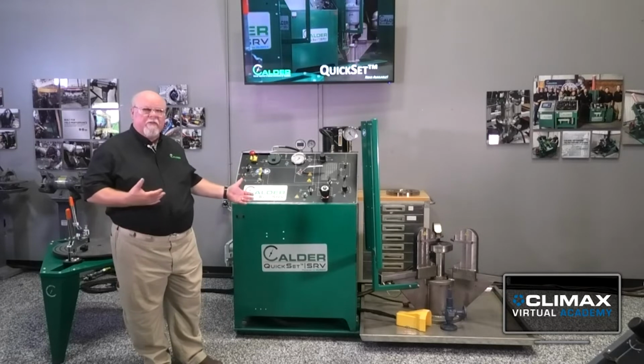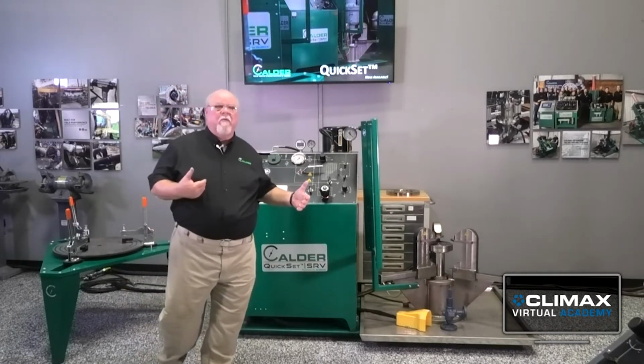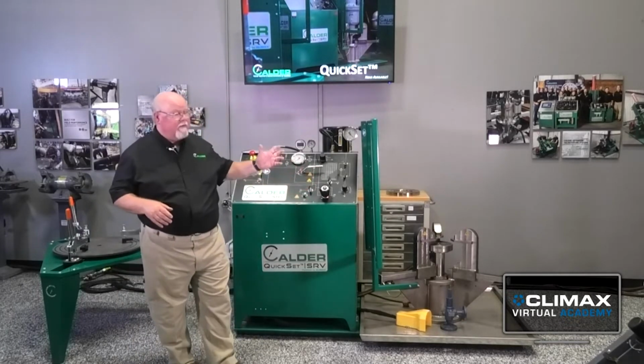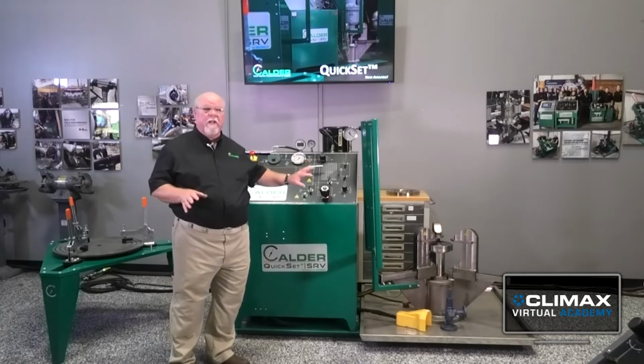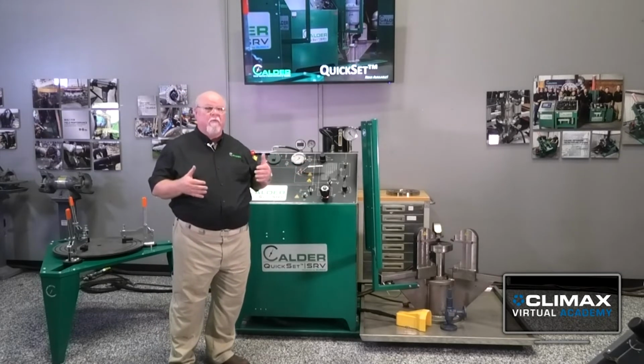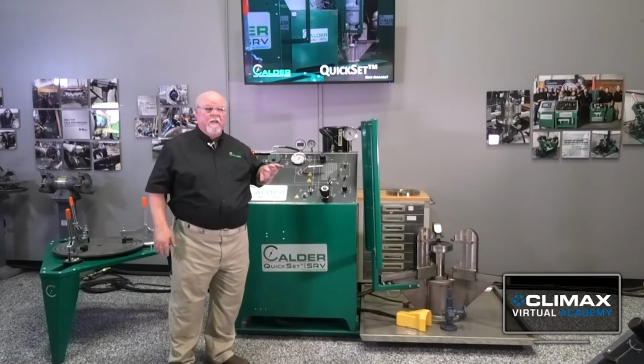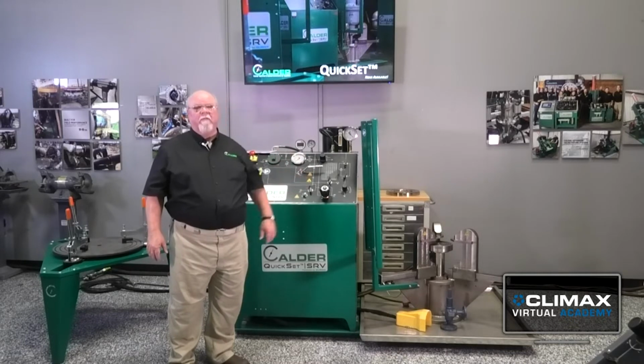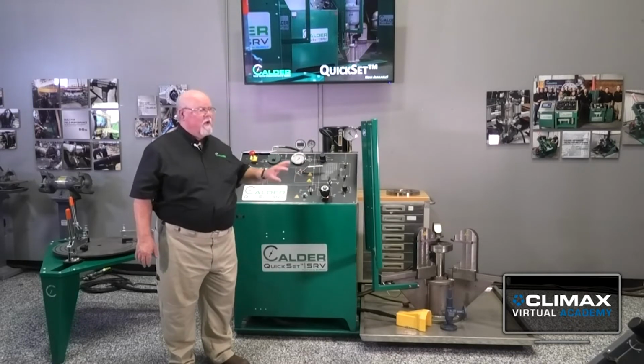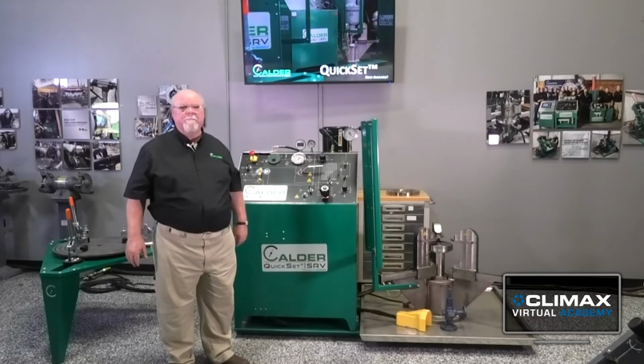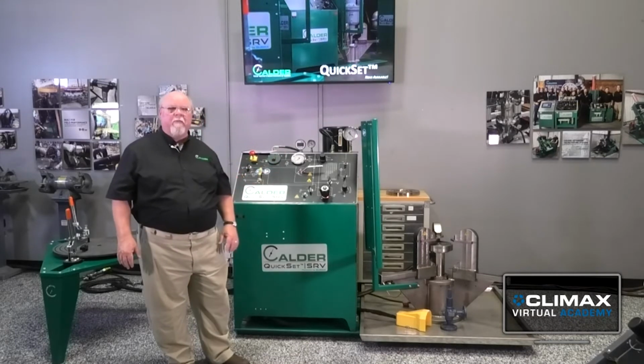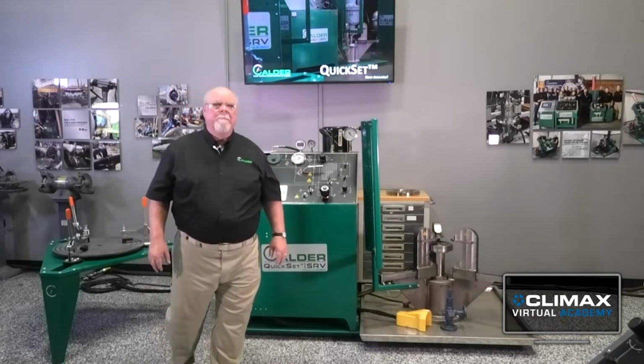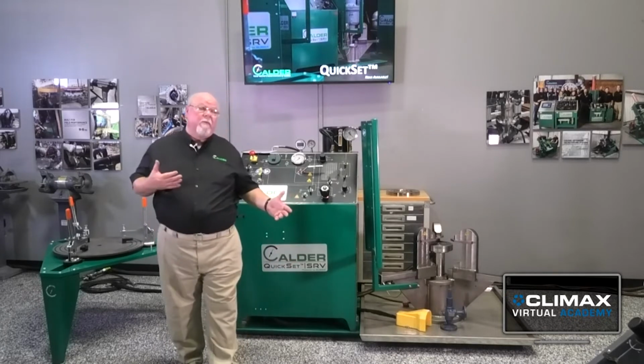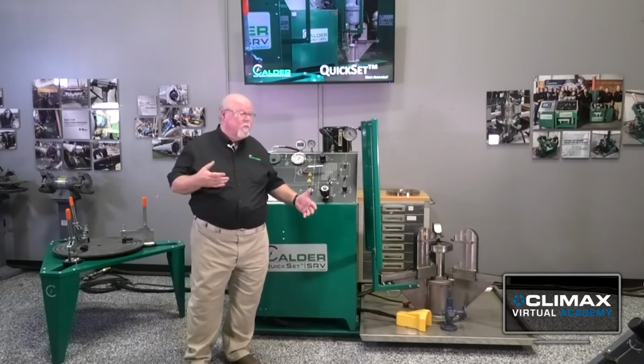The last one I want to mention today is that when making adjustments to a valve that's on the test stand with pressure underneath it, we want to make sure that the test pressure sitting underneath the valve during the adjustment period is low enough that the valve's not going to open on us when we make the adjustment. So be cautious of that. There are provisions we'll get into in a little bit. Now that we're comfortable with our surroundings, we're going to proceed.